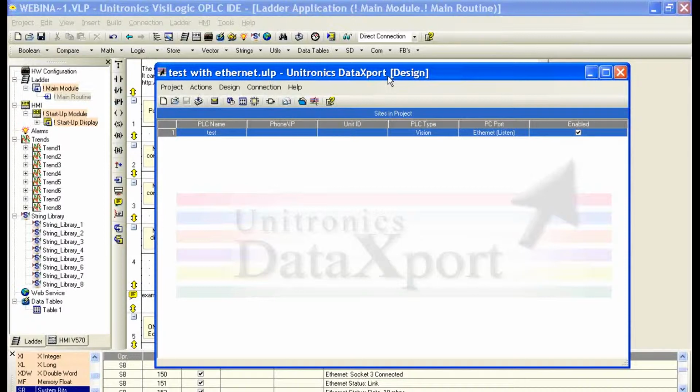Another powerful example is a lookup table. I can give you an example of an analog input sensor that doesn't follow a linear output profile. We have a couple choices. We can use a formula function block if we can determine a formula to use, or we can use the data table as a lookup table. If we have a certain analog input value, we can search the table, find out what row it is, and read out that piece of information in the adjacent columns that pertain to that value. So there's a lot of things we can do with the data table.